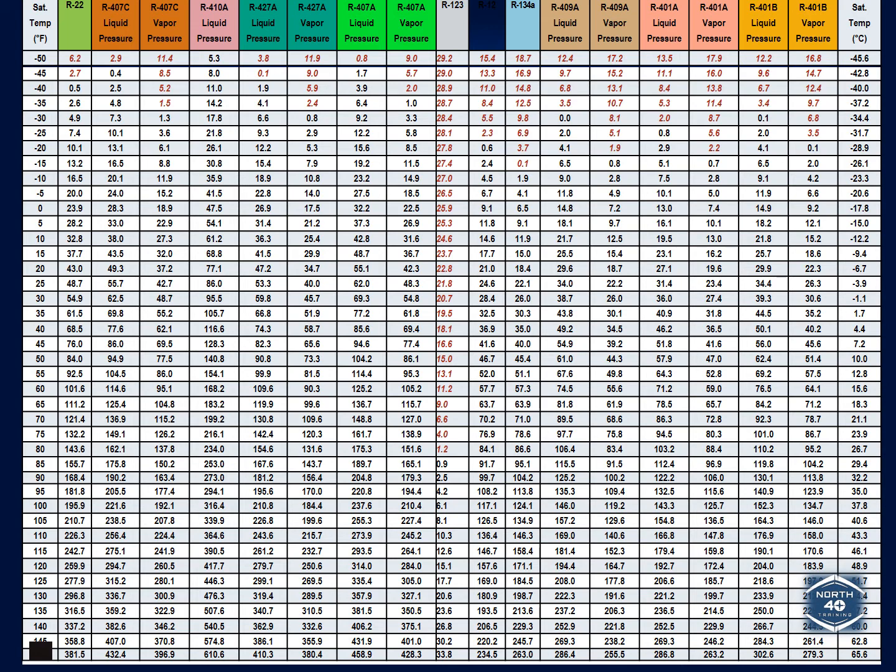If you go over to 410A, which is the fourth refrigerant across the top from the left, not counting the first square, which is temperature, going down that left-hand side. So if you go to 410A and follow it down to 60 psi, which you'll come out at 61.2. If you look to the far left in the temperature column, that correlates to 10 degrees.